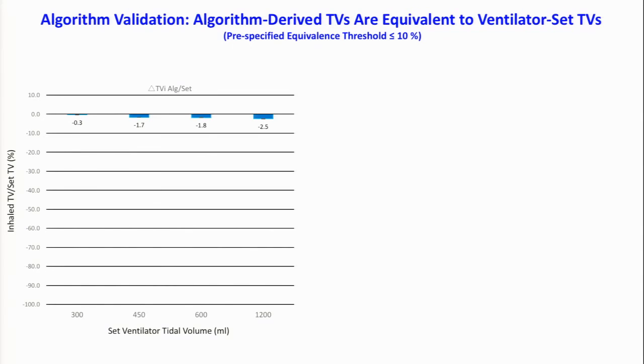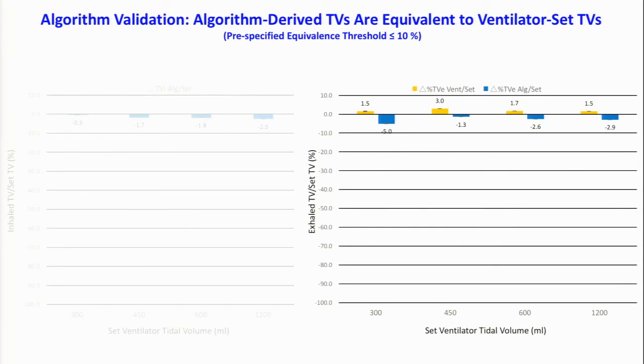So how we've done as far as validation is concerned: our tidal volume validation is incredibly tight. These were experiments in which we dialed the tidal volume into the ventilator and then looked at what our algorithm was computing for the calculated tidal volumes, and we're off by just a few percent. We have a pre-specified equivalence threshold of about 10% because the ventilator manufacturers themselves quote a breath-to-breath variability in their own accuracy of about 10%. We're well within that, with tiny error bars because there's so little variance in the data.